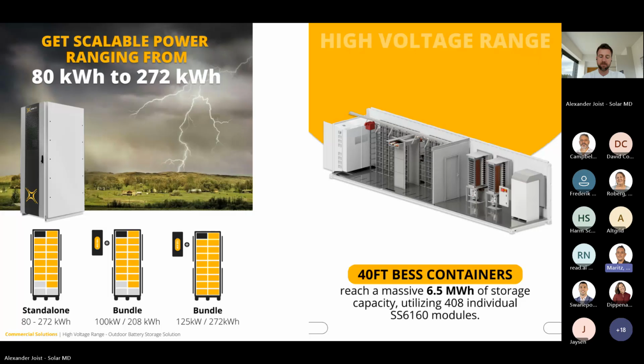And the other one - on your previous data sheet, it showed the usable capacity on a 0.3C rating, but the new data sheet doesn't show the usable capacity. So what is the capacity of these new cells - is it 90%, 100%, 70%? Generally it's 100% usable energy. I mean, we obviously recommend depth of discharge to 90%, or down to 10%, so 90% of energy used within a system is definitely the safer way, but generally it's 100%, and 100% of the energy in there is usable.